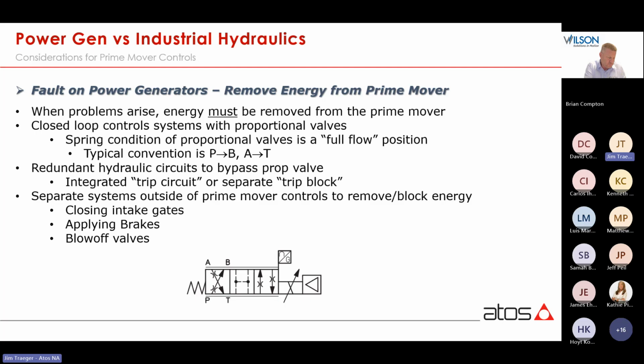And keep in mind, there will also be other ways to stop the prime mover which operate outside the closed loop hydraulics. We could close intake gates on hydro turbines to cut off water from the whole turbine system. We can apply brakes on wind turbines, which will stop the blades from spinning, even if the wind keeps blowing. Or we use blow-off valves on steam turbines to allow the steam to safely bypass the turbine.